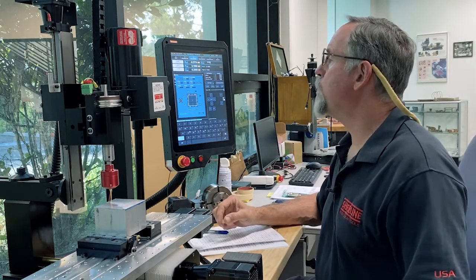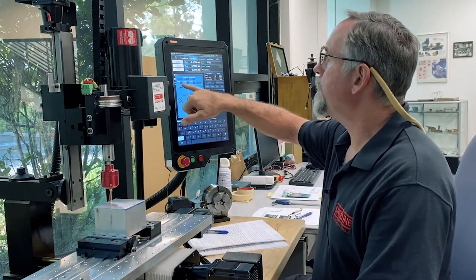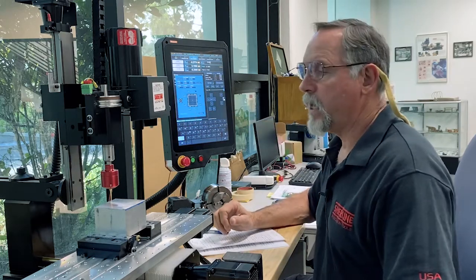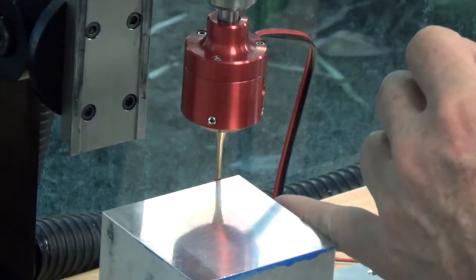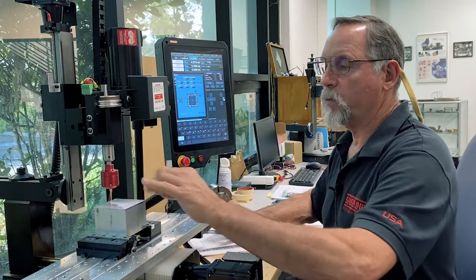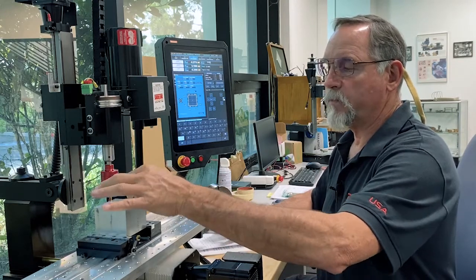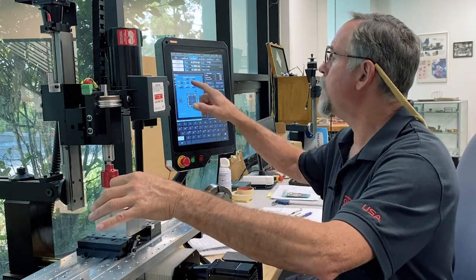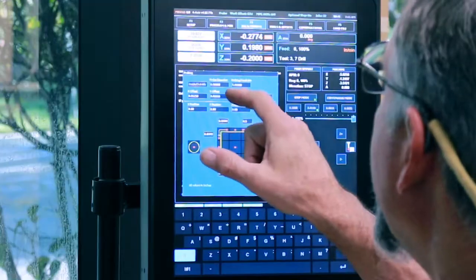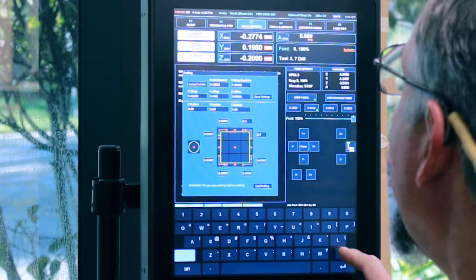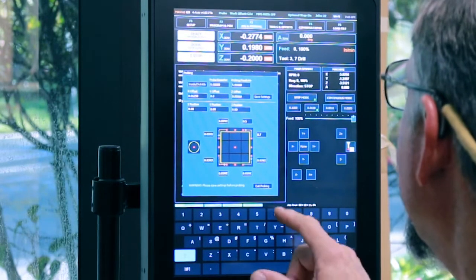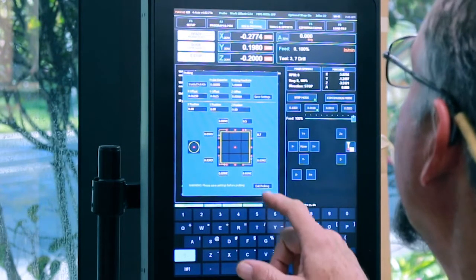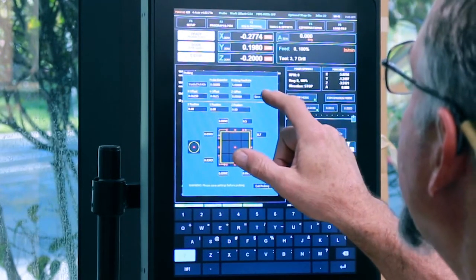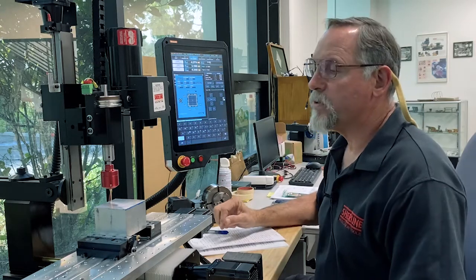Now the next one, right now I've got an offset of 0.0625 for the X, so when it touches on the X it's going to compensate half the width of the probe tip to find the actual edge. On the Y I don't have anything, so I have to add my offset amount into my Y-axis also, 0.0625, and again I have to hit Save Settings. So the settings are saved.